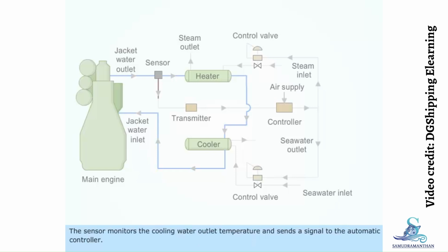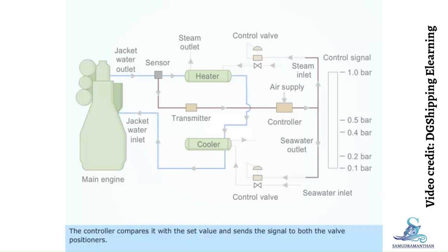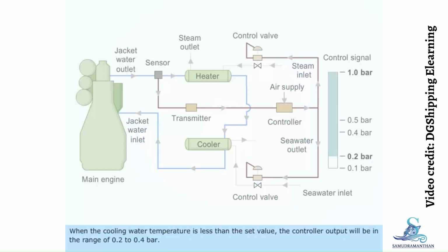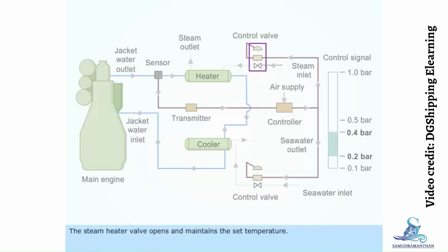The sensor monitors the cooling water outlet temperature and sends a signal to the automatic controller. The controller compares it with the set value and sends the signal to both the valve positioners. The automatic controller output to the valve positioners ranges from 0.2 to 1 bar. When the cooling water temperature is less than the set value, the controller output will be in the range of 0.2 to 0.4 bar. The steam heater valve opens and maintains the set temperature.